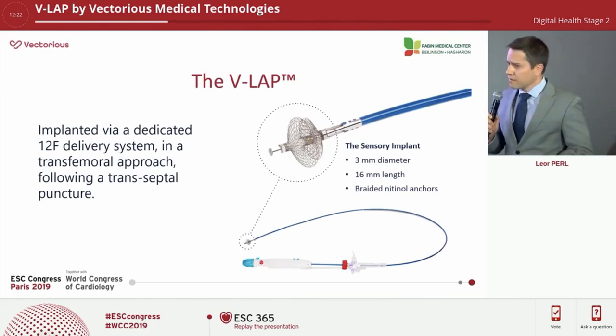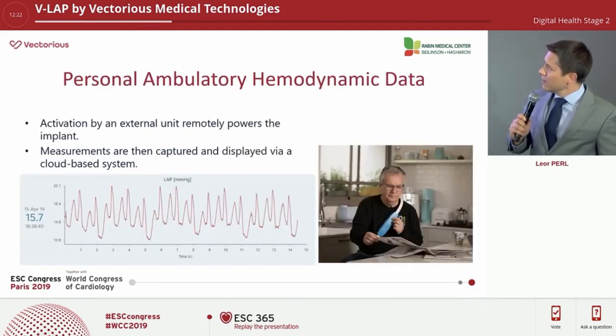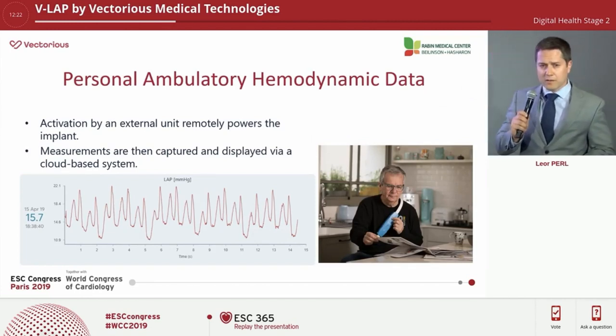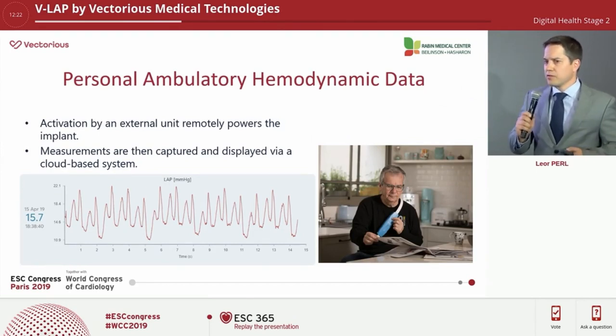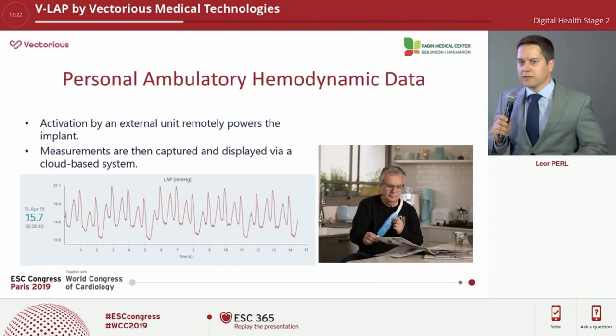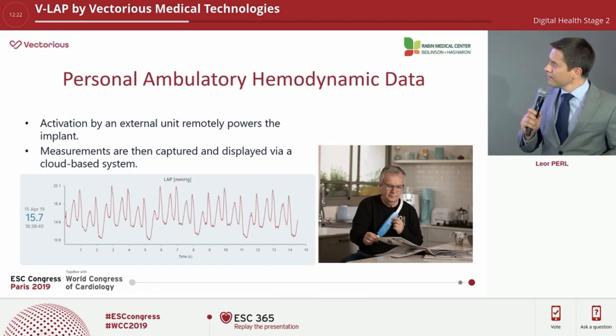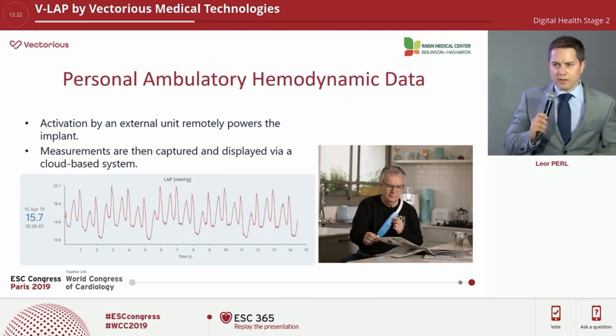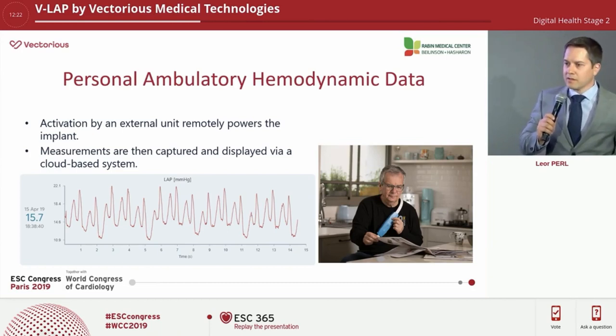The sensor is really small — three millimeters in diameter and 16 in length — and it is coupled with an external unit. The sensor is battery-less; upon the push of a button, it starts transmitting data after relaying energy to the sensor by inductive coupling. What you capture are beautiful high-definition waveforms of actual cath lab data, with all the V-waves and A-waves, from home.